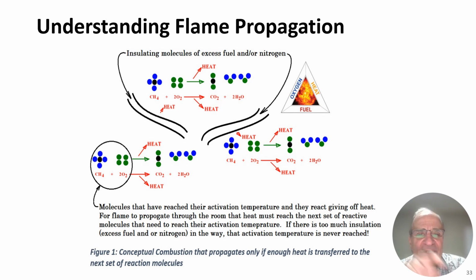Why? Because I'm within the flammable range of that fuel. For methane, it happens to be between 5 and 15%. For hydrogen, it's much broader. For acetylene, it's something like, I don't know the exact number, maybe 4 to 80% fuel and air mixture. It's a very wide flammability range. We'll probably see that on one of the slides yet to come.